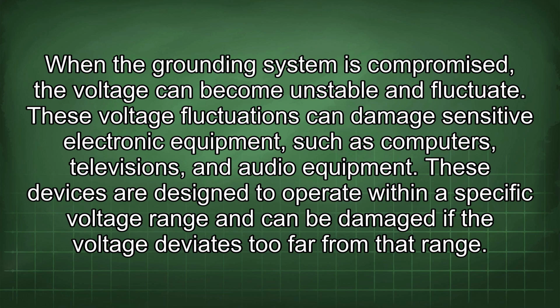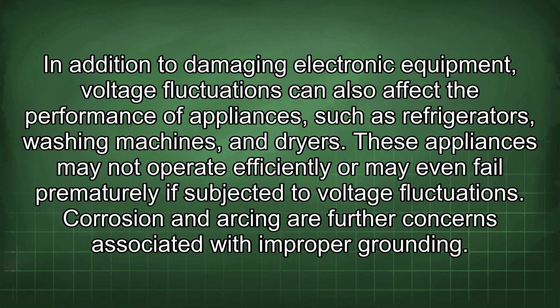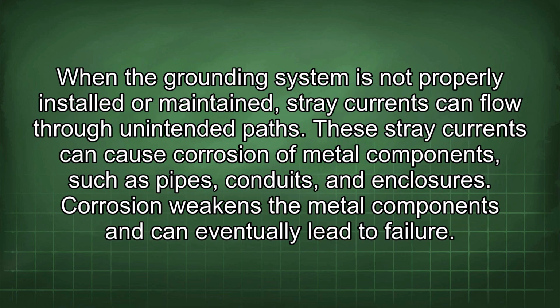In addition to damaging electronic equipment, voltage fluctuations can also affect the performance of appliances, such as refrigerators, washing machines, and dryers. These appliances may not operate efficiently or may even fail prematurely if subjected to voltage fluctuations. Corrosion and arcing are further concerns associated with improper grounding. When the grounding system is not properly installed or maintained, stray currents can flow through unintended paths. These stray currents can cause corrosion of metal components, such as pipes, conduits, and enclosures. Corrosion weakens the metal components and could eventually lead to failure.